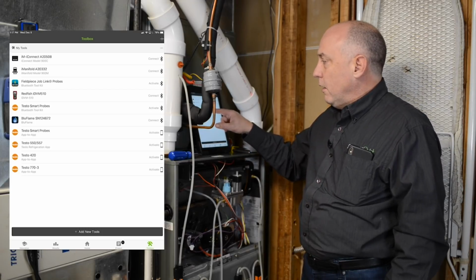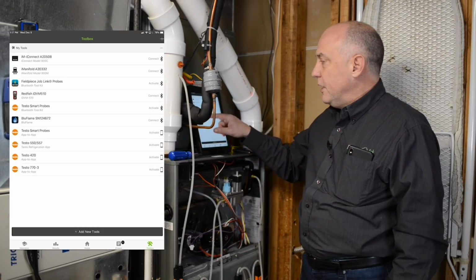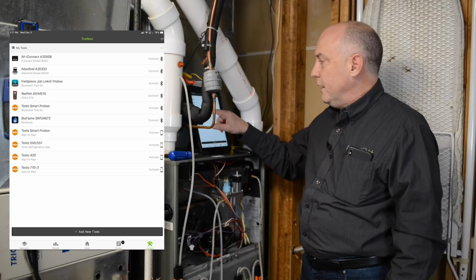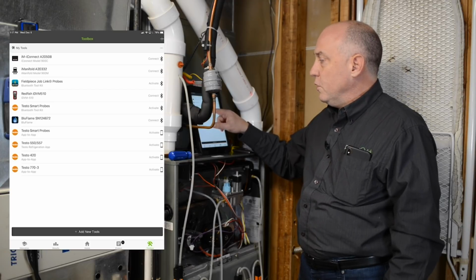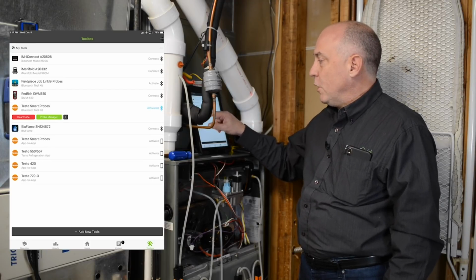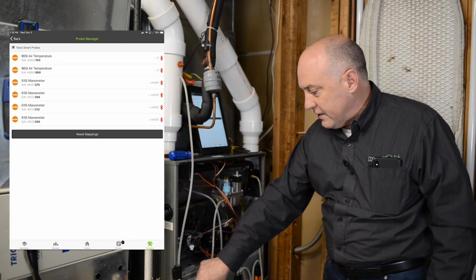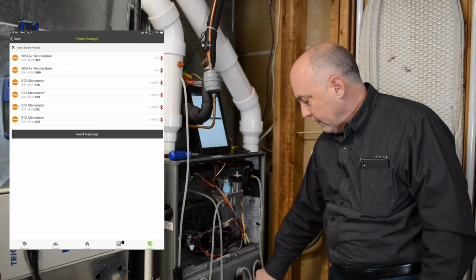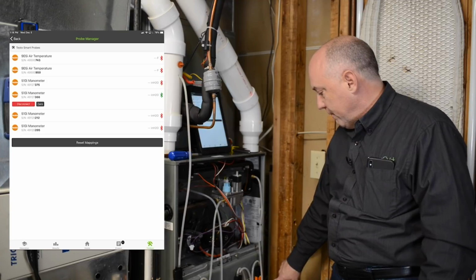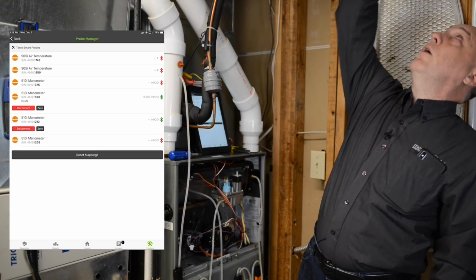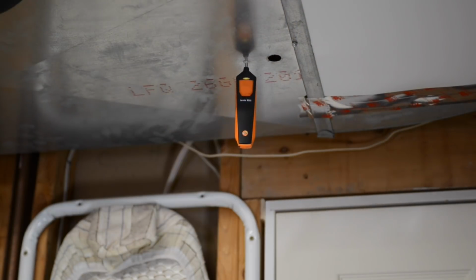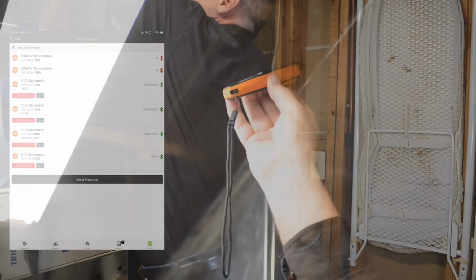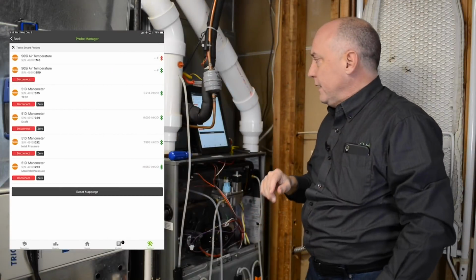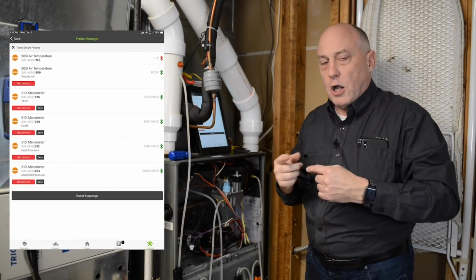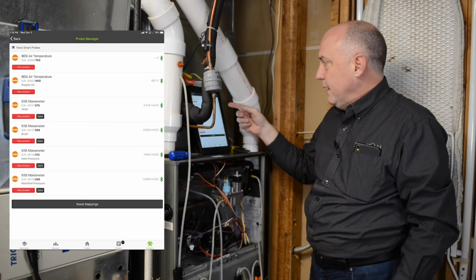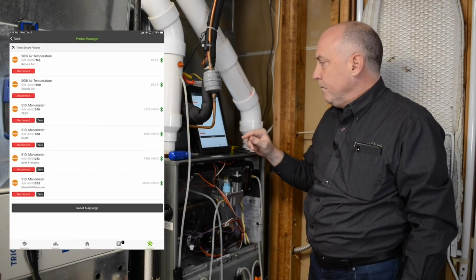So I'm going to go ahead and literally all I'm going to do is turn on my Testo apps here. So I've got Testo Bluetooth Toolkit. I tap on that. If I go into my probe manager, what you'll see as I turn these guys on is that they will come in automatically into the app. And I've got one up here for my supply air temperature, and I'm going to turn on one more here for my return air temperature, and you'll see all these guys coming in, automatically syncing in the application and bringing in their temperatures behind them.